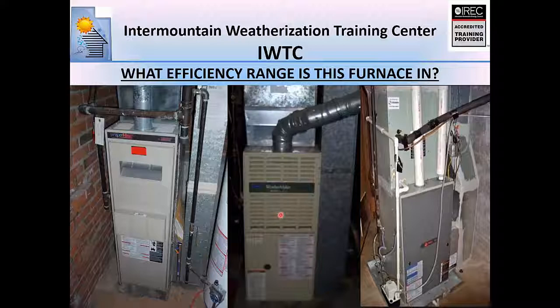Now we'll get into it. I've got some more slides on it. We'll get into it. But there are safety devices built into these that will typically shut them down. But when these backdraft, they actually cause flame rollout. And they can actually cause all kinds of damage to the furnace and start a fire. But we'll get into that a little bit more as we go through this.